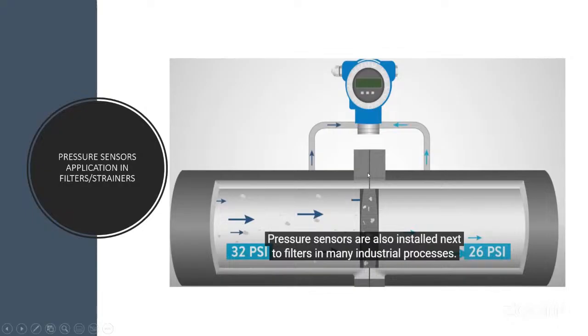This application is widely used in cleaning systems, effluent treatment plants, and many others to check pressures. We also use it, for example, in checking leakages between tanks where there are big differences in pressure. So a small program is written on the controller side, and it does these checks and transmits the information to the logic controller, where an alert will be sent to the HMI operator, so the technical personnel will know exactly the current condition of the filter.